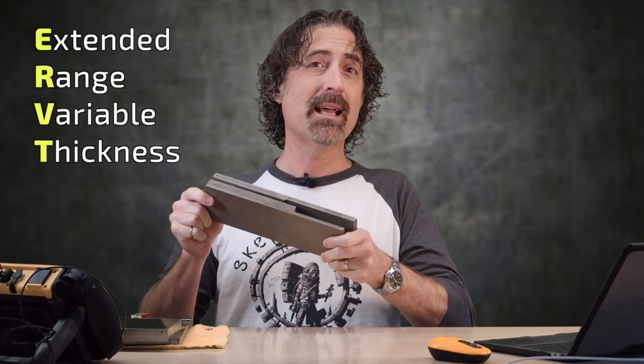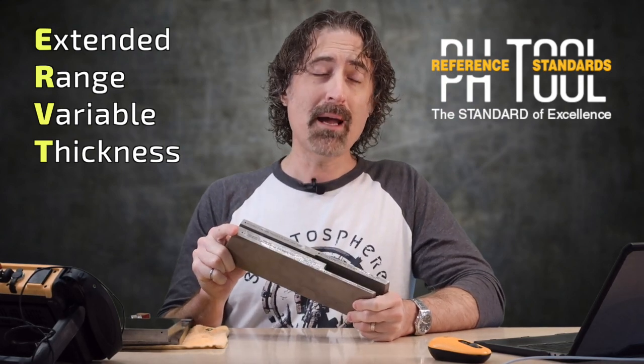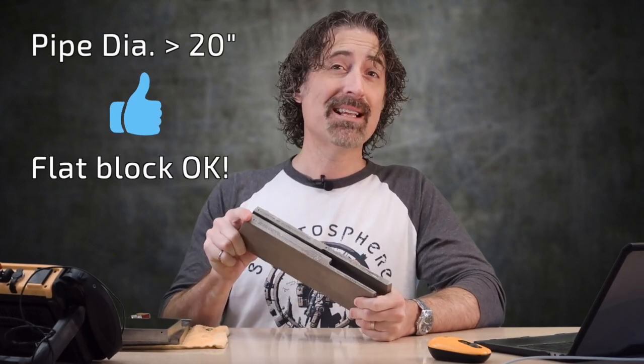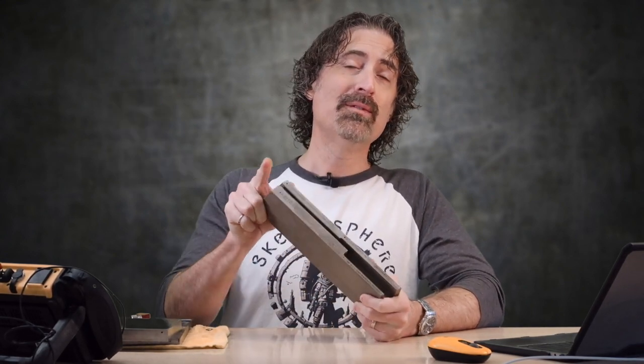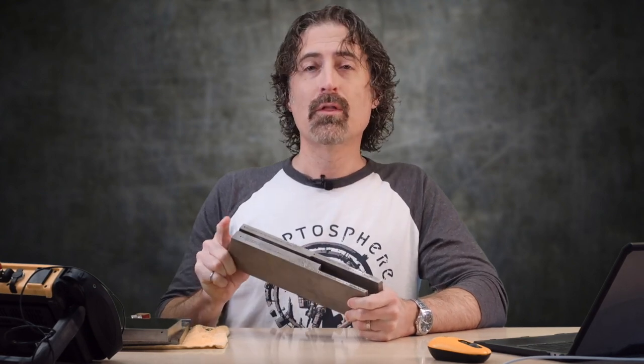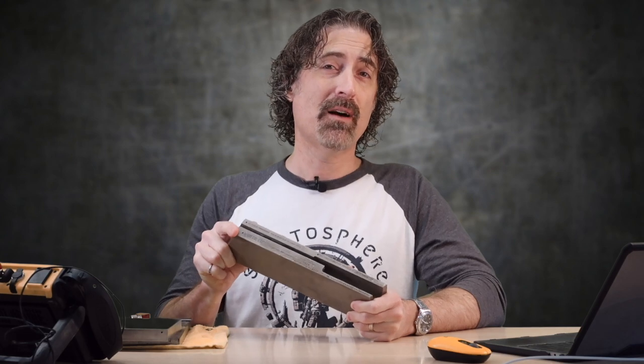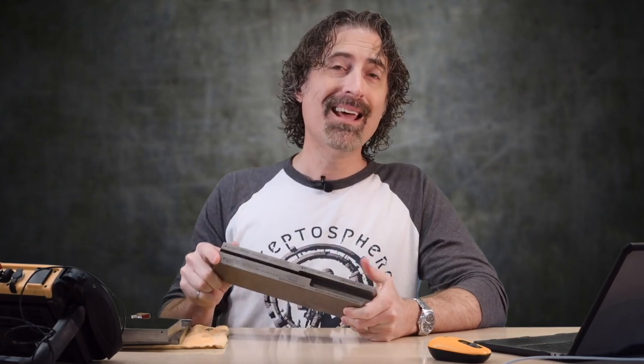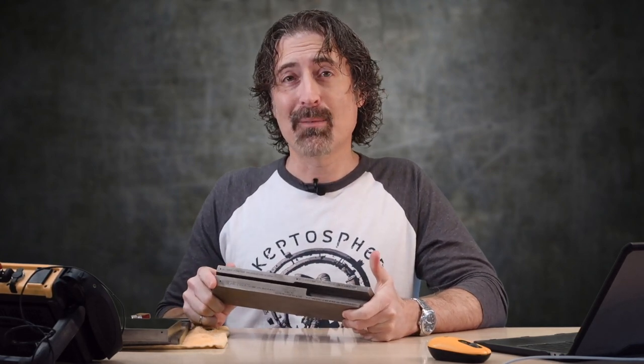And this one is my extended range variable thickness or ERVT block from PH Tool. This is what we use for piping applications over 20 inches in diameter. That's where ASME lets you get away with a flat block. We've talked about this part before. The rules in ASME for piping state that the calibration block has to be within 25% thickness of the pipe. That means sometimes you're hauling around a lot of calibration blocks.